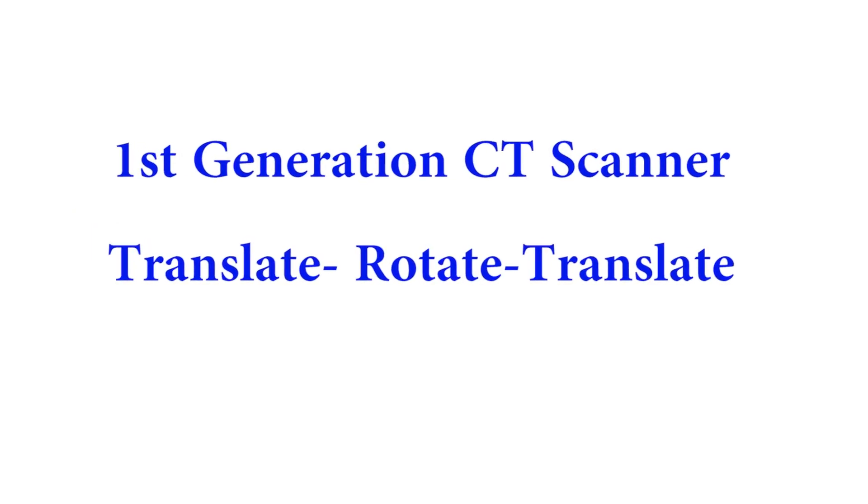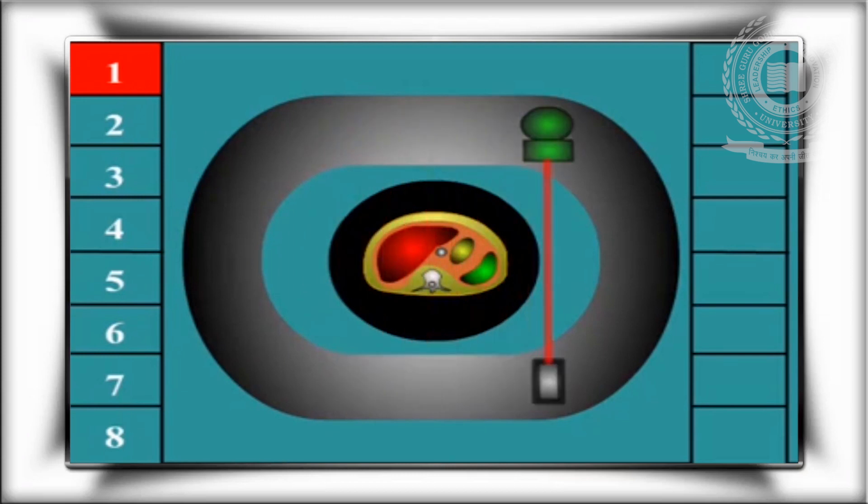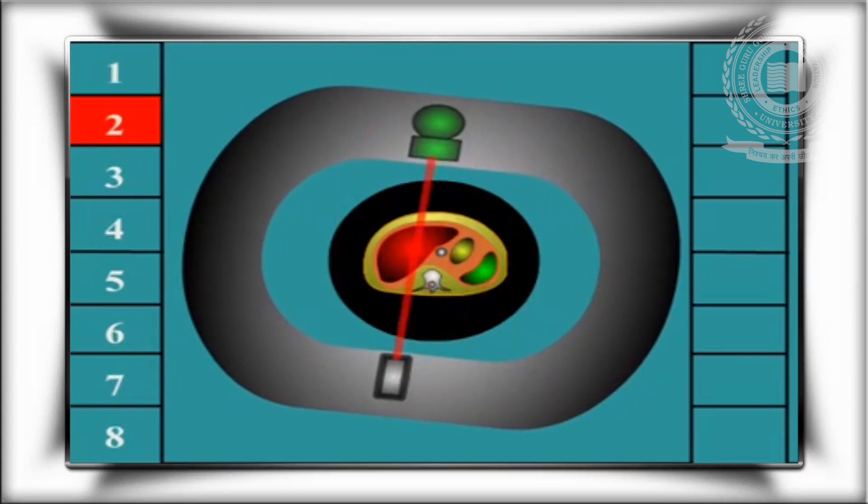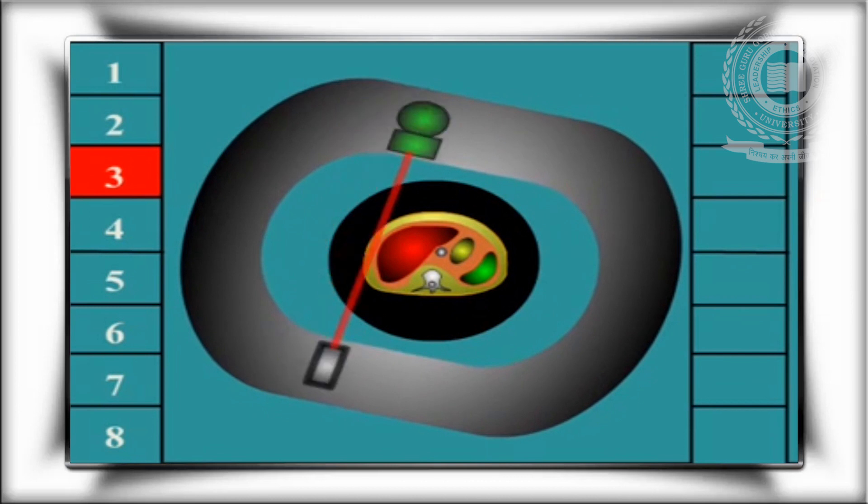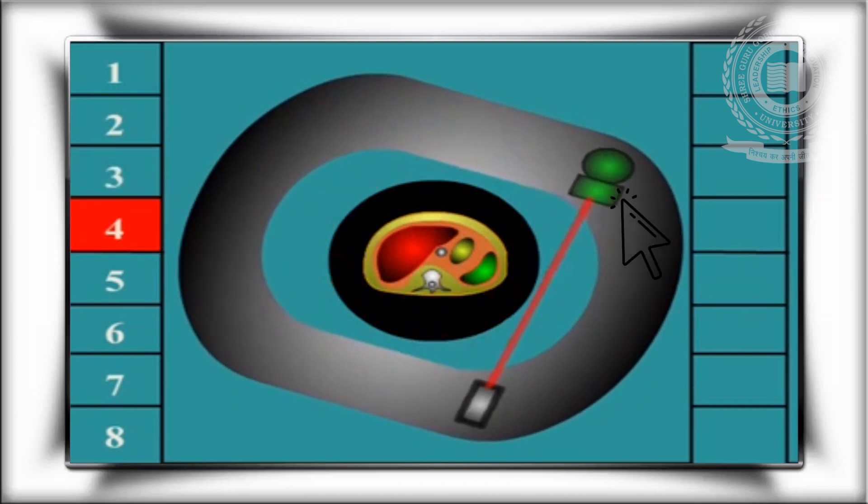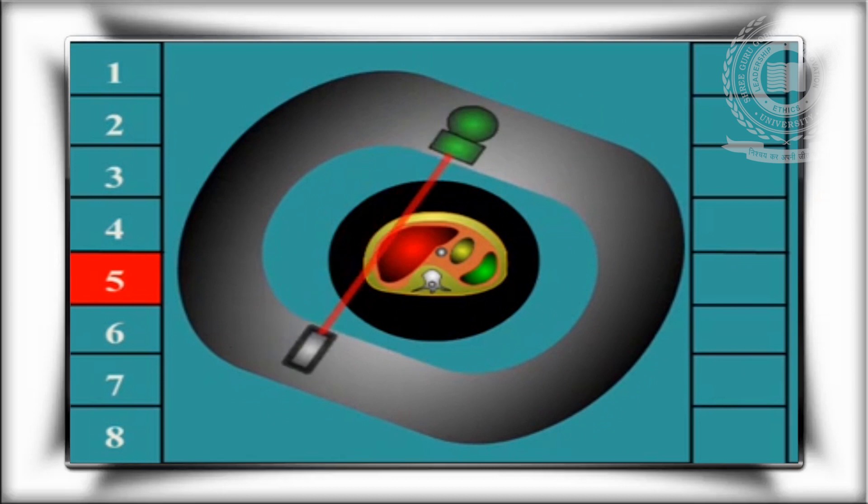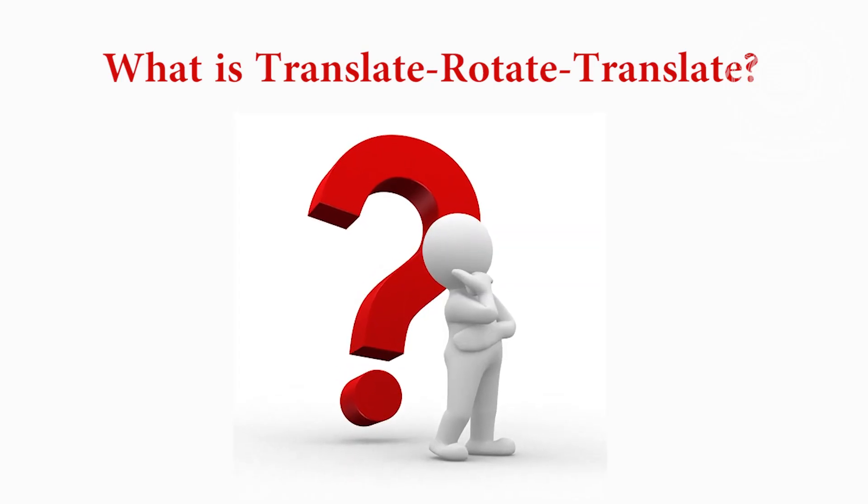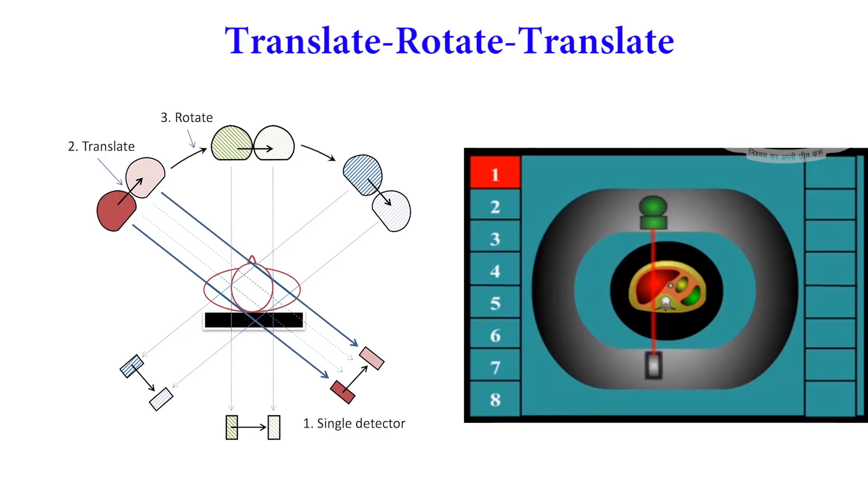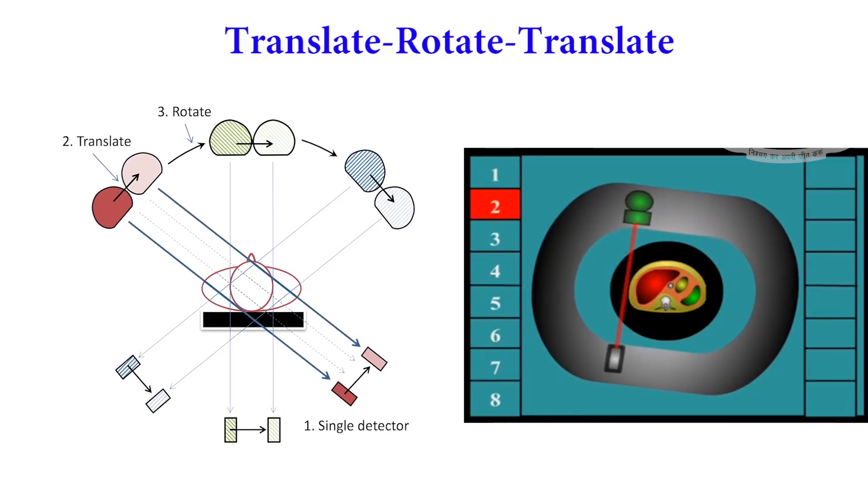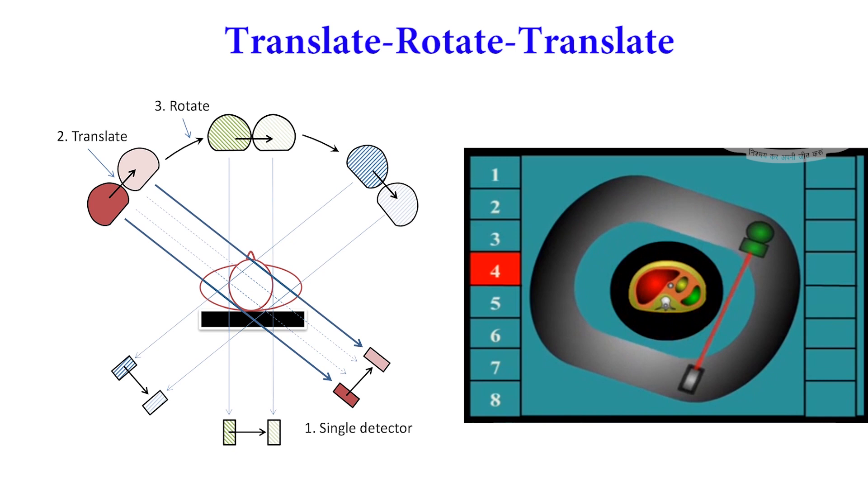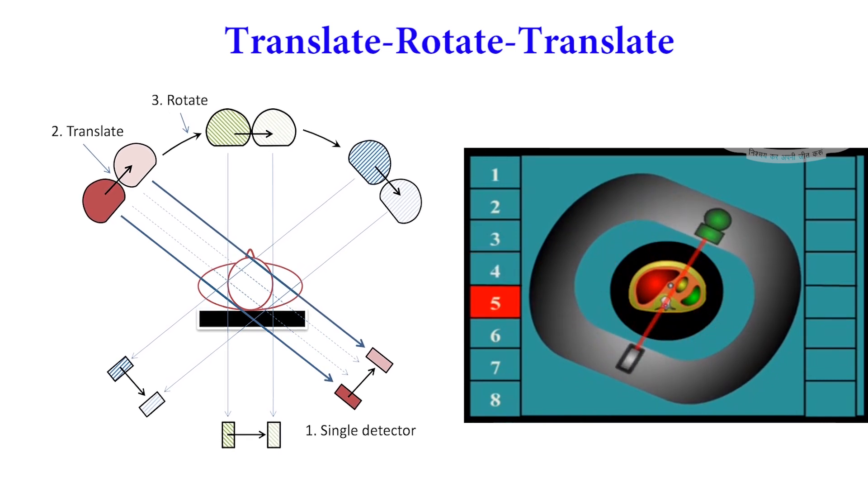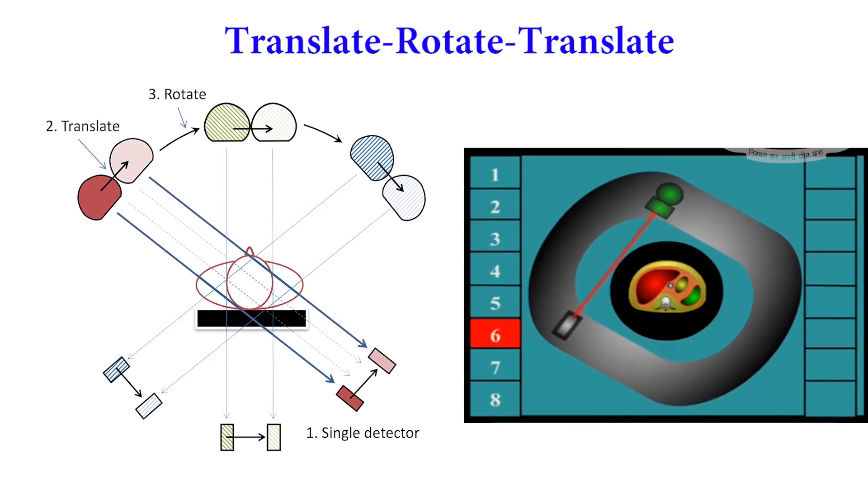First generation CT scanner. As you can see in this animation, first generation CT scanner is known as translate-rotate-translate. In this animation, green one is X-ray tube, red linear line is showing the X-ray path, and lower box is detector. What is translate-rotate-translate? Because in this equipment, X-ray tube first moves in translate motion, then rotates, and again moves in translate motion around the patient.